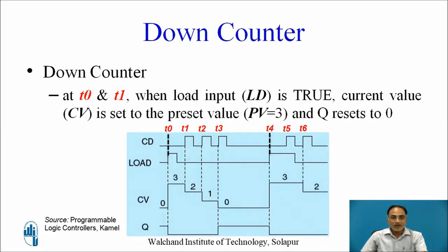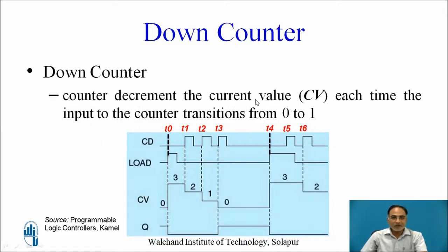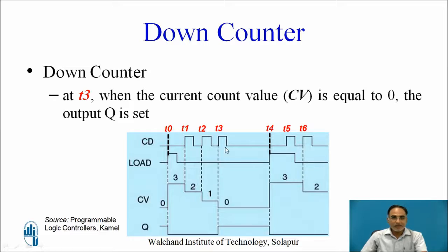Let us understand the down counter with the help of a waveform. At T0 and T1, the load signal is true, so the current value CV is set to the preset value — CV is set to 3 and Q resets to 0. The counter decrements the current value each time the input transitions from 0 to 1. At T1, T2, T3 the counter is decrementing each time, and at T3 when the current value equals 0, the output Q is set.